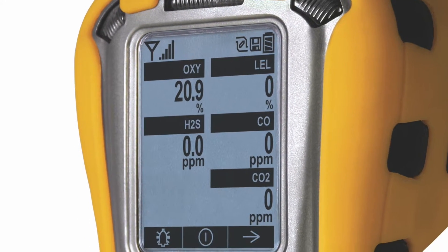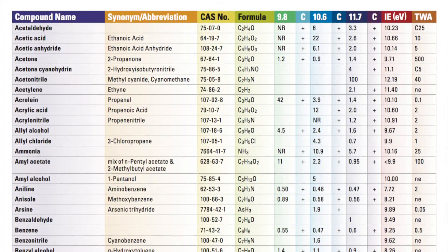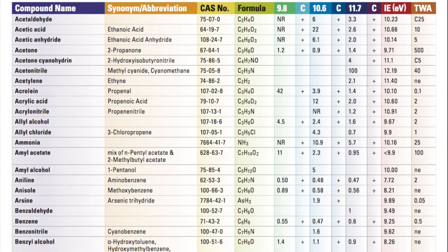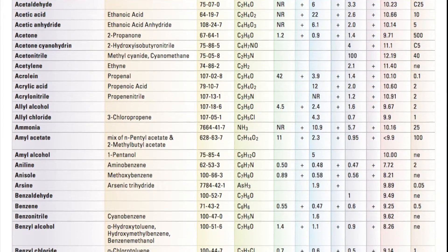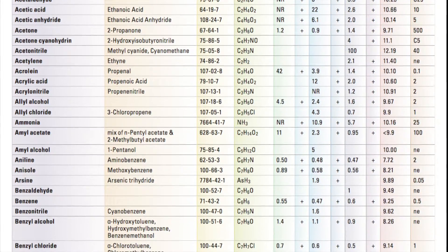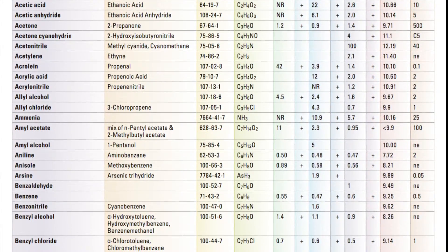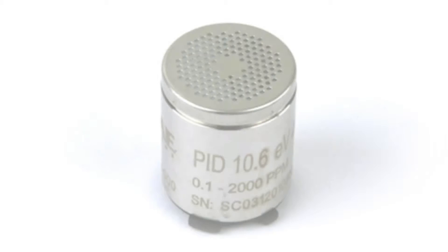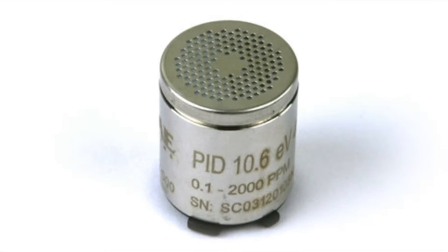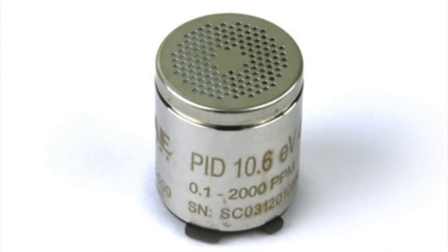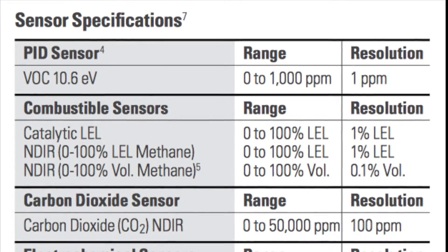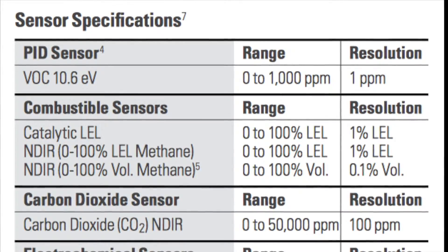The sensors available for the Light and Multi-Ray include a 10.6 electron volt photo ionization detector for broad spectrum VOC measurement, with a range from 0.1 to 5,000 ppm and a resolution of 0.1 ppm on the Multi-Ray, and a limited range of 1,000 ppm with a resolution of 1 ppm on the Light.